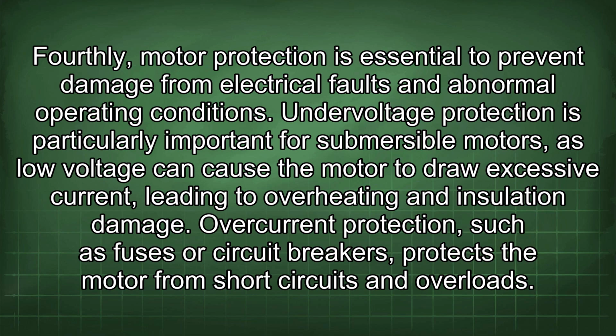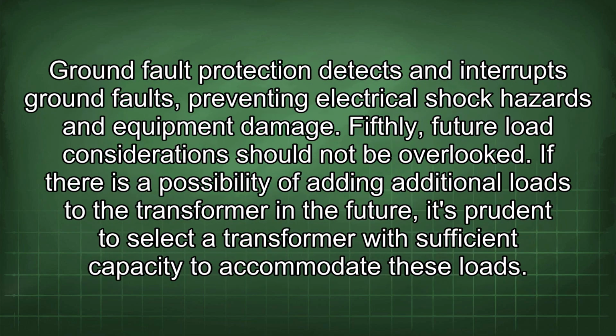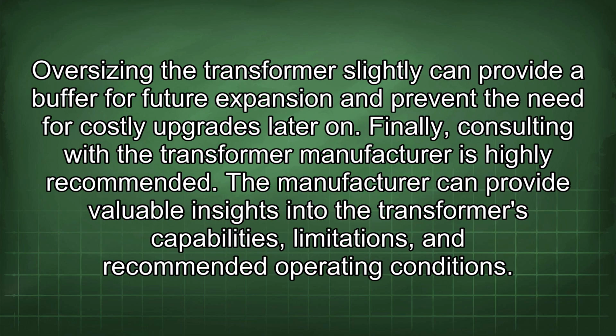Undervoltage protection is particularly important for submersible motors, as low voltage can cause the motor to draw excessive current, leading to overheating and insulation damage. Overcurrent protection, such as fuses or circuit breakers, protects the motor from short circuits and overloads. Ground fault protection detects and interrupts ground faults, preventing electrical shock hazards and equipment damage. Fifthly, future load considerations should not be overlooked. If there is a possibility of adding additional loads to the transformer in the future, it's prudent to select a transformer with sufficient capacity to accommodate these loads. Oversizing the transformer slightly can provide a buffer for future expansion and prevent the need for costly upgrades later on.